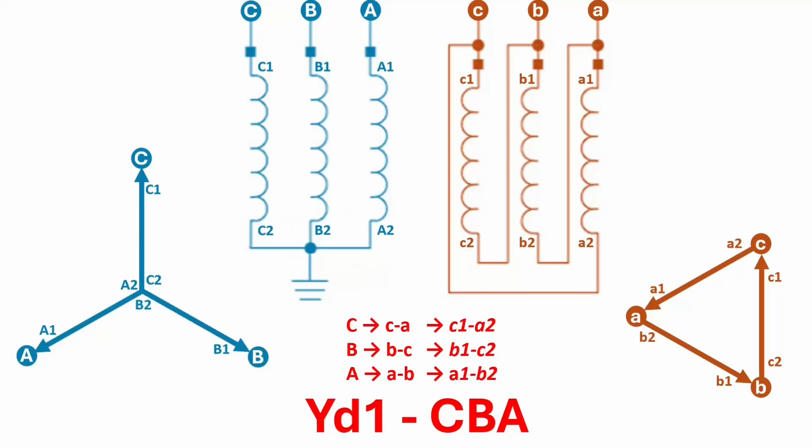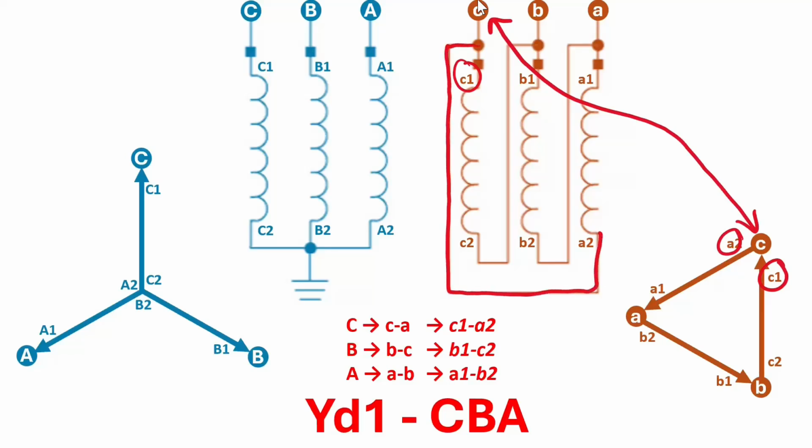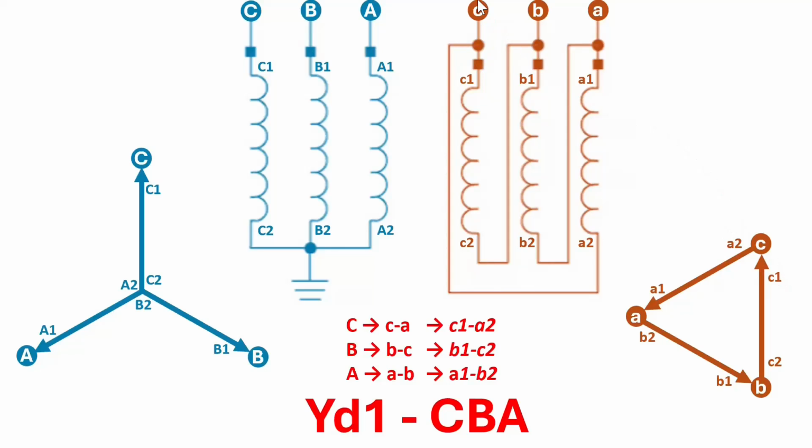However, on the secondary, what happened here? Well, our C phase connection right here is right here. So I'm just going to mark those the same. So you have C1 that connects to C1. That makes sense. The other one is A2. Is that true? Follow that bushing around, come around. It goes around to A2. Yes, it does. And that matches everything that we've written down right here in the middle of the page, just as a reference, okay? So this is exactly what I meant by it.